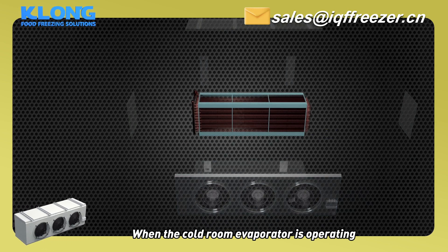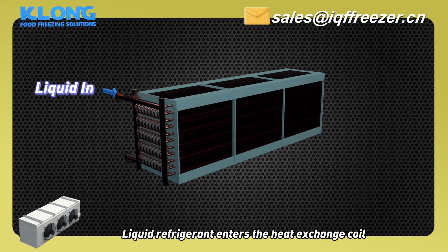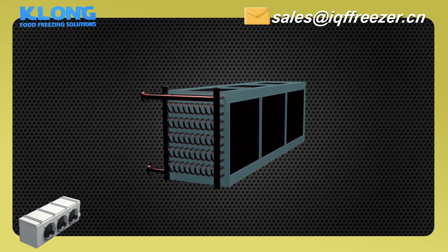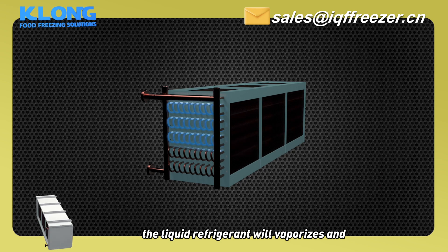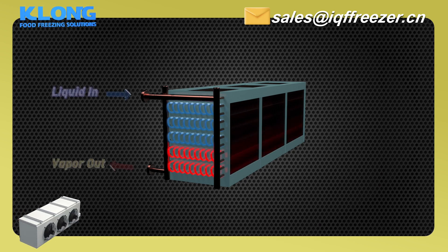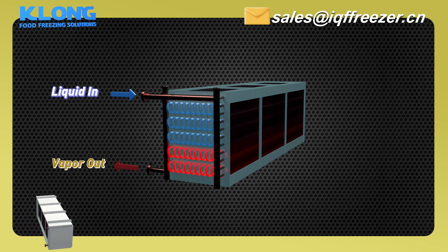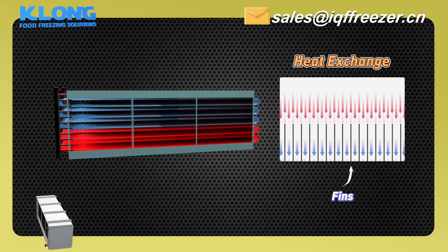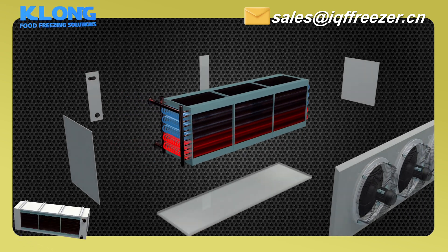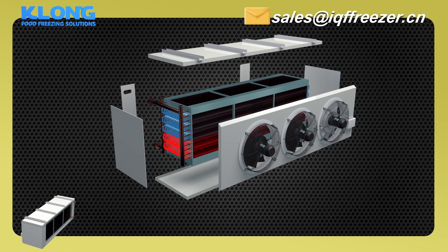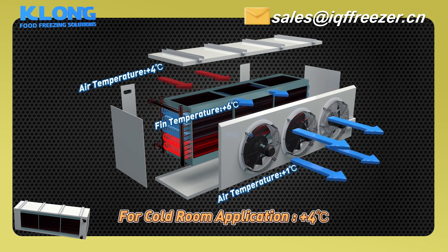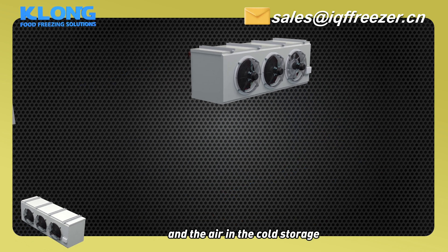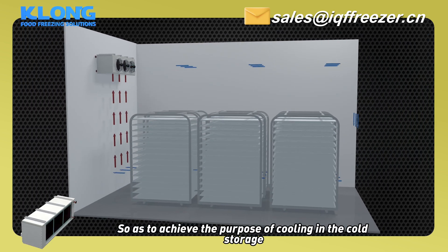When the cold room evaporator is operating, liquid refrigerant enters the heat exchange coil through the liquid separator. The liquid refrigerant will vaporize and absorb the heat. The axial fan is responsible for the convection circulation between the fan and the air in the cold storage, so as to achieve the purpose of cooling in the cold storage.